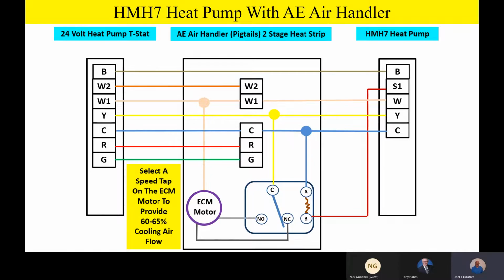The normally open contact on the relay is where we select a speed tap on the motor to provide 60 to 65% airflow. If you do some quick math in your head, or take your calculator out, you're going to find that 60% of 1,200 CFM is about 720 CFM. I had a contractor comment the other day that when we hook up to that normally open contact, that's 60%, but they didn't have the capability of hitting exactly 720, and that happens on the ECM motor on the AE air handler. The idea was, what if I'm at 650, or at 675? Well, that's close enough.